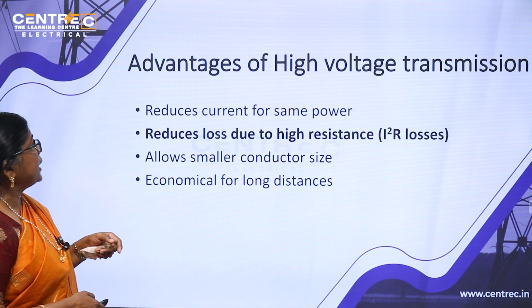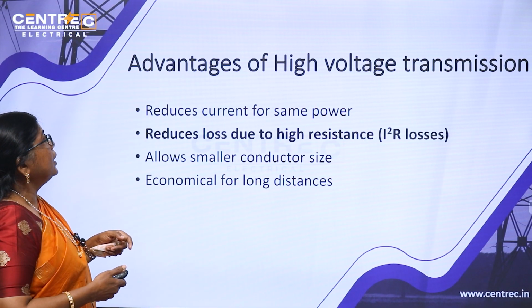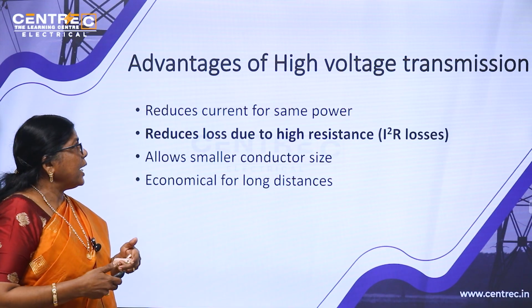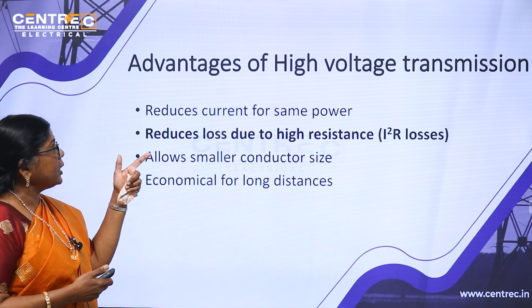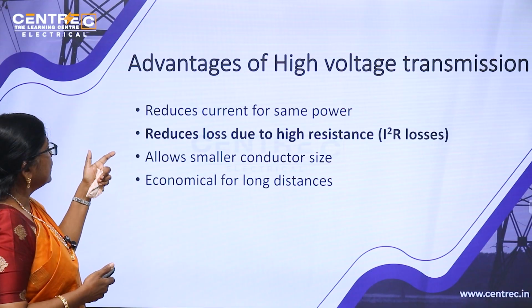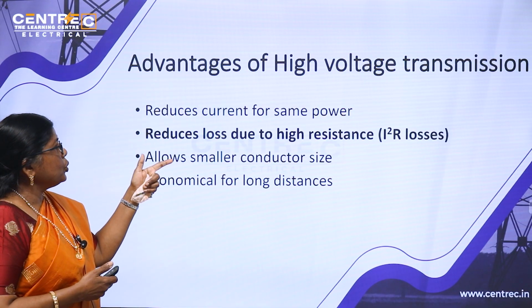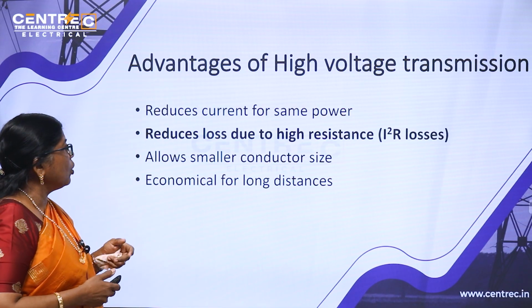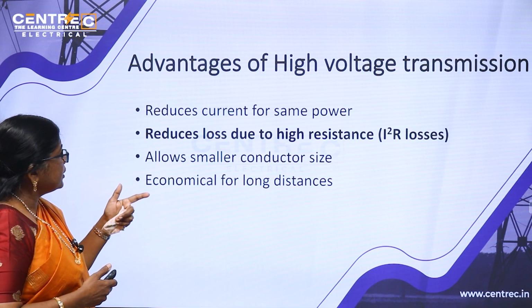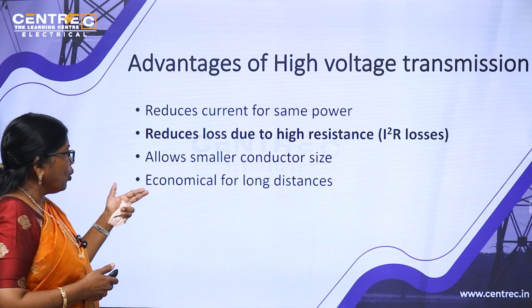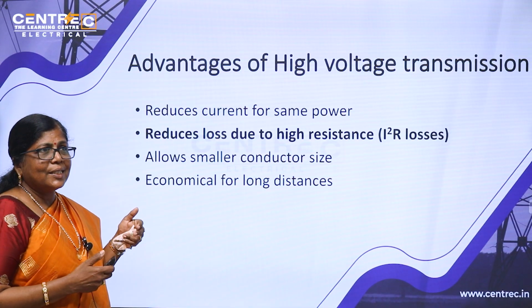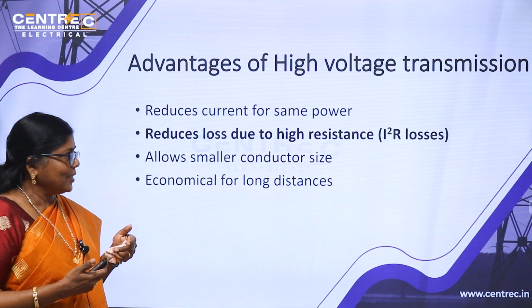Advantage of high voltage transmission. Why do we transmit at high voltage? Because it reduces current for the same power, which then reduces loss due to resistance, the I squared R losses, allows smaller conductor size, and is economical for long distance. That is the basic law of resistances.